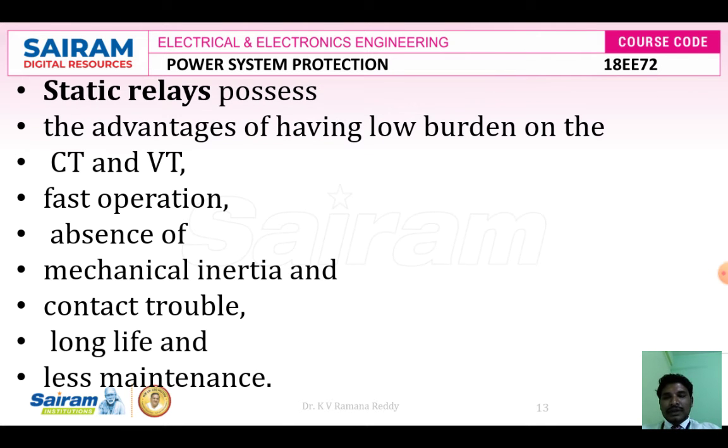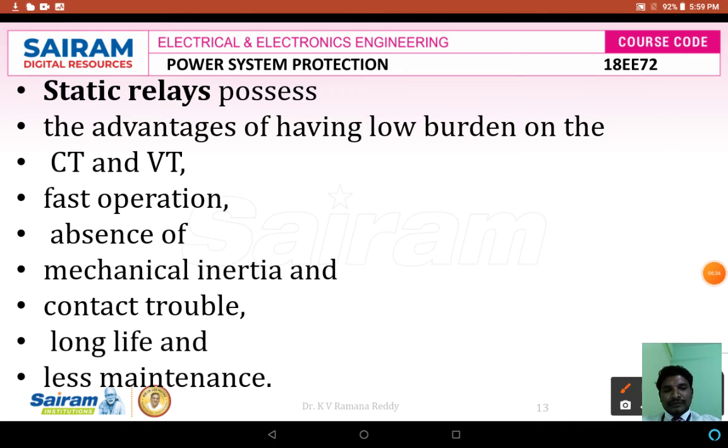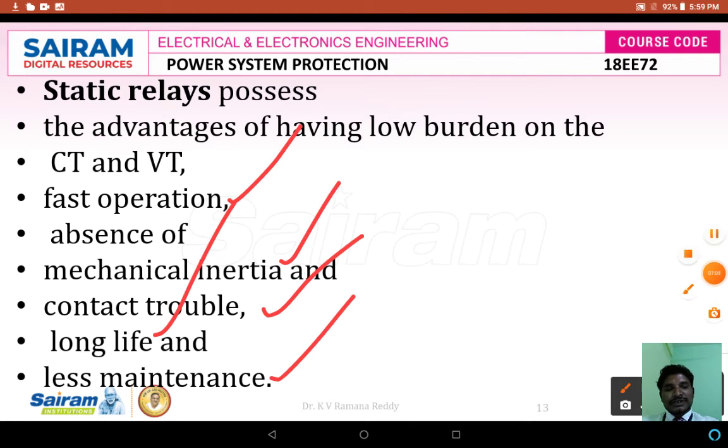Static relays possess the main advantages because they do not present much burden. That means the burden on CT and VT is very less, and they have fast operation because they are fast switching devices. Due to static relays there is an absence of mechanical inertia, because there is no need to overcome the weight of opening and closing of the circuit breaker switch. Contact troubles are not there, and it gives long life because there is no arc to be extinguished due to the operation of the circuit breaker, and it requires less maintenance, especially for static relays.